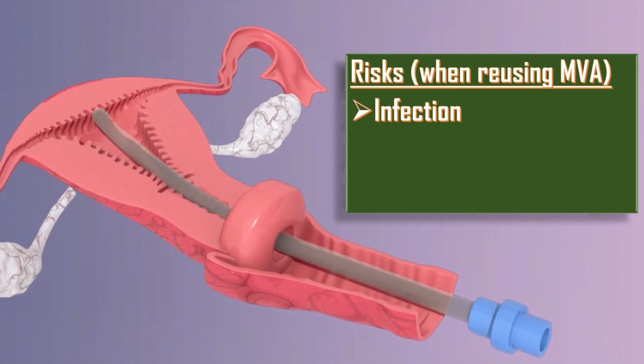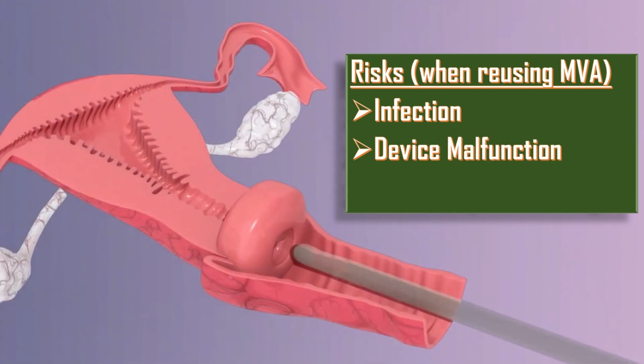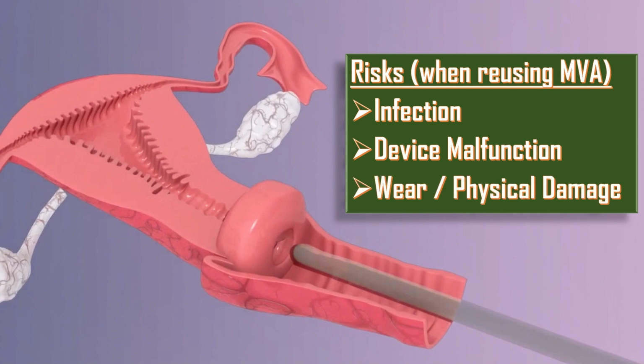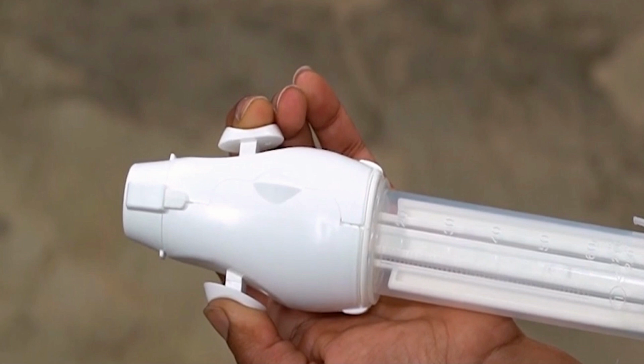Risks when reusing MVA components. First of all, infection transmission if cleaning and sterilization is inadequate. Secondly, device malfunction, that is, loss of vacuum, leaks after repeated cycles, wear and physical damage to components leading to procedural failure. Always follow the device manufacturer's IFU, it is authoritative.